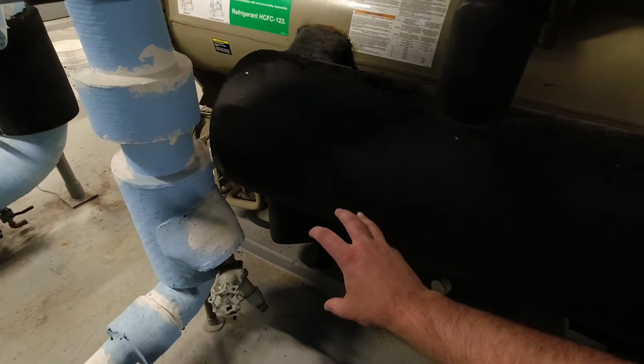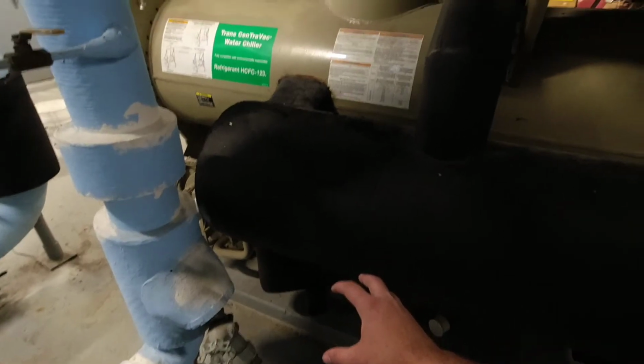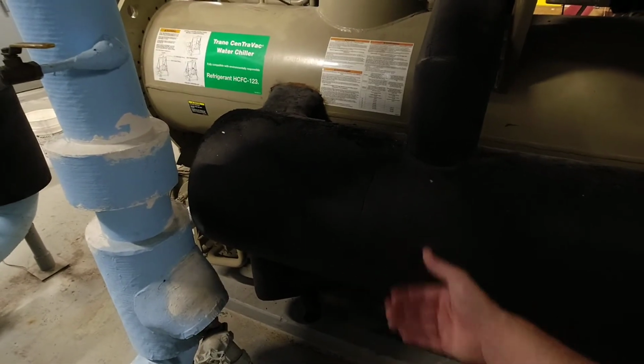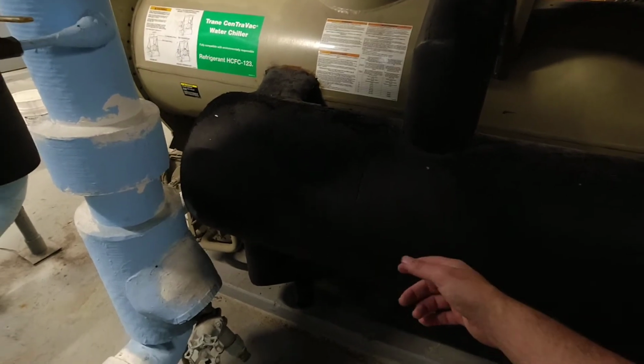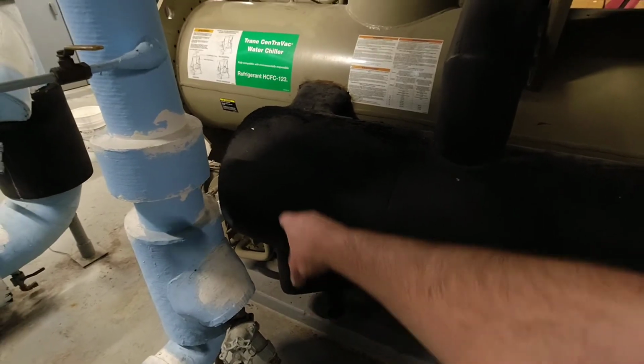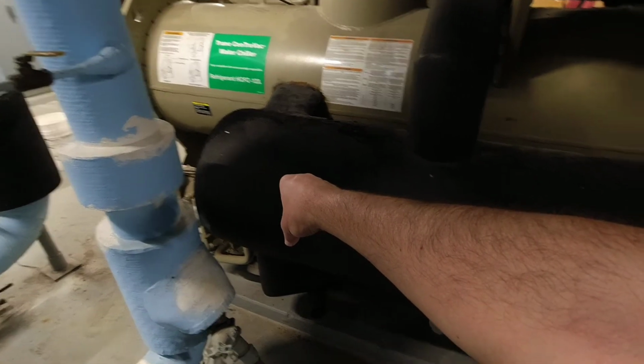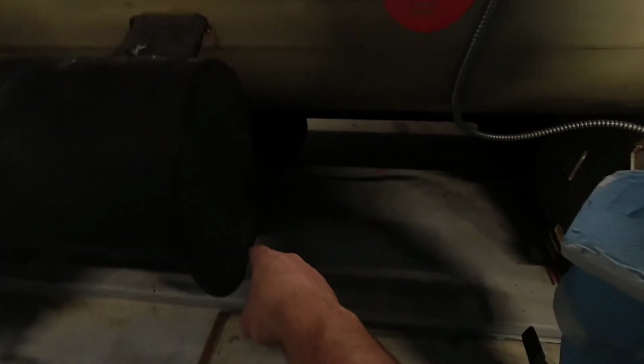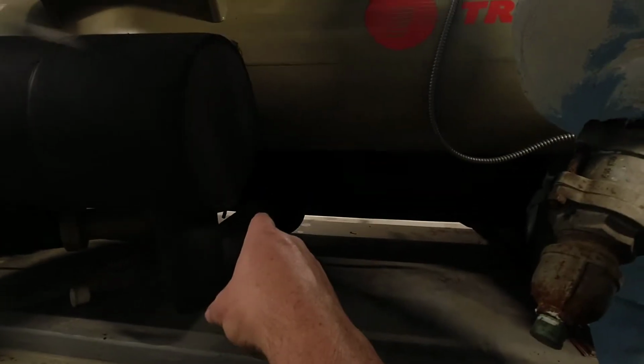Liquid line comes out, and then it hits the very first flash plate. That flash plate is where we go from the liquid line to the two-phase line and up into the economizer. So you're going to pull through the liquid line. You go through a flange, which inside that flange, again, there is a flash plate. And that flash plate is just a perforated plate that the refrigerant flows through to flash it, just like it would through an orifice. It's going to come up into the economizer, go through the economizer, back out the bottom, and go up under into the evaporator on the back side and through another flange and flash plate there at the evaporator.